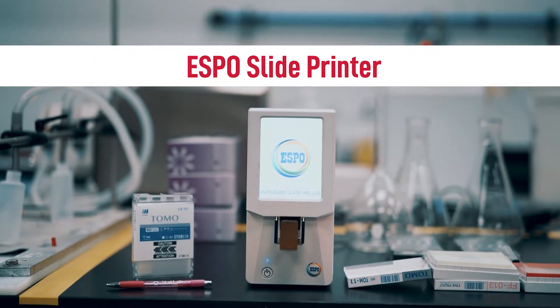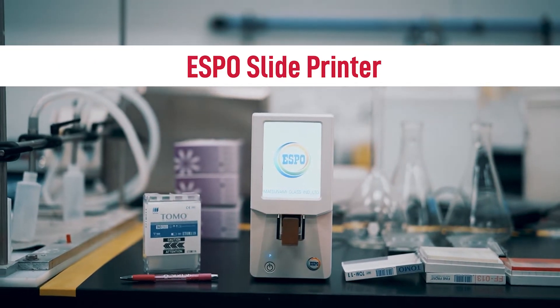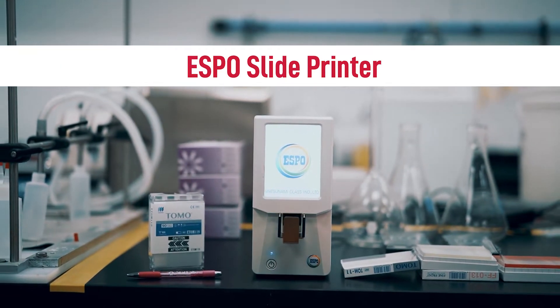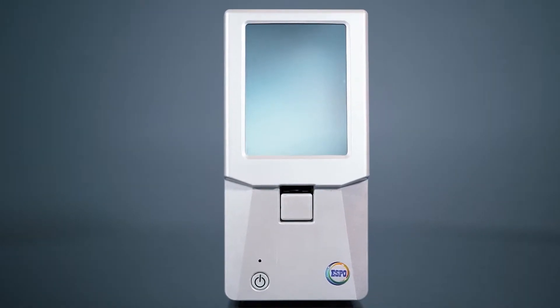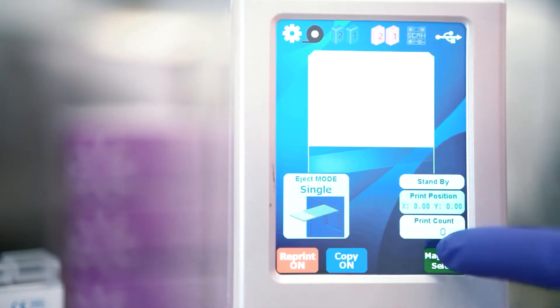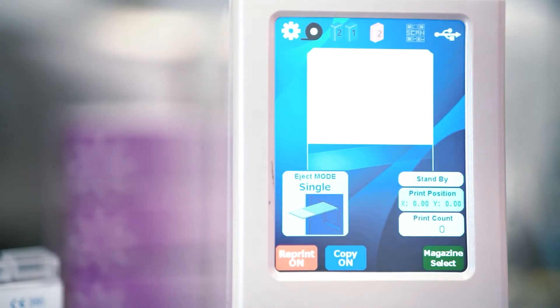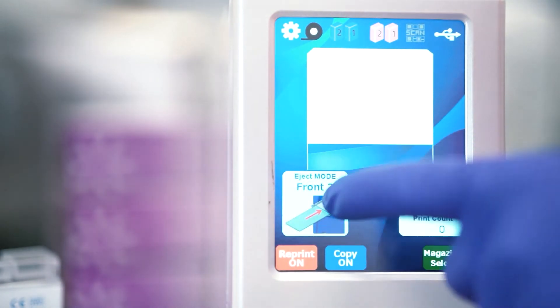The ESPO on-demand slide printer is a powerhouse with a small footprint, measuring less than 5 by 10 inches to neatly reside by your microtome. A color touchscreen provides an intuitive interface to select printing options.